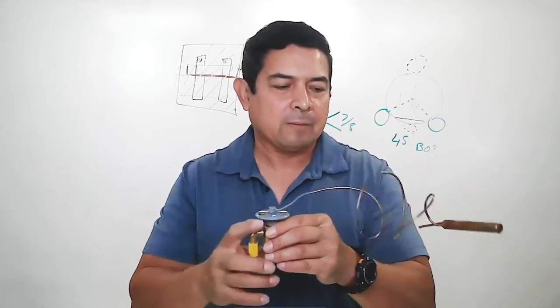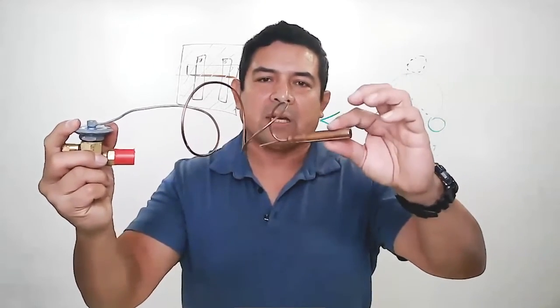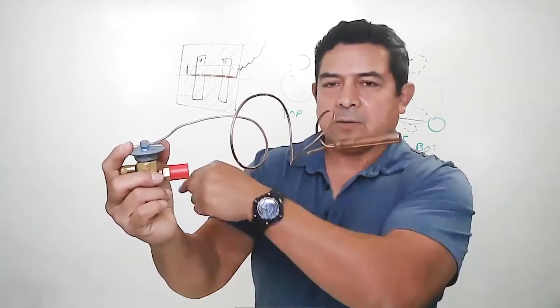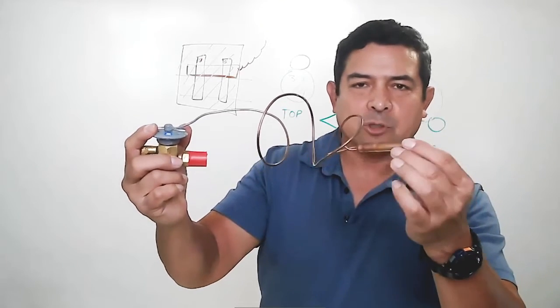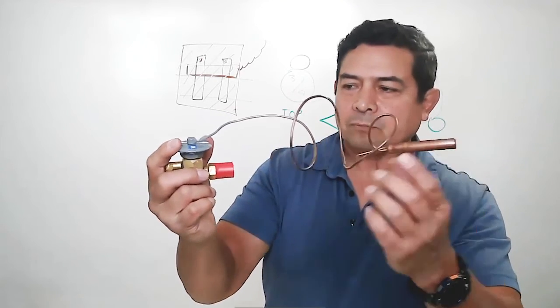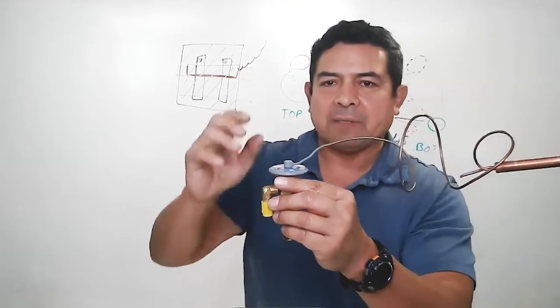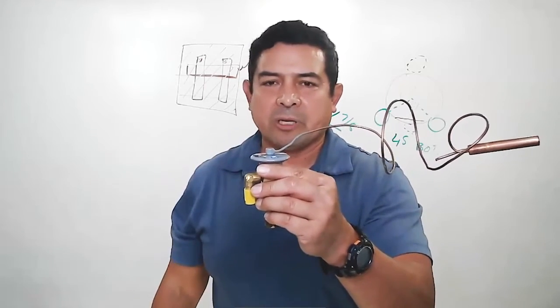Why do you want to take it apart? Because in here, we're going to have some kind of gas or some kind of liquid. Typically, it's the same type of refrigerant that you have in the system. So if this is a 410A system, you may have a couple of drops of 410A in here. You overheat this, the temperature goes up too much, you're going to pop the diaphragm, you're going to break the power head.